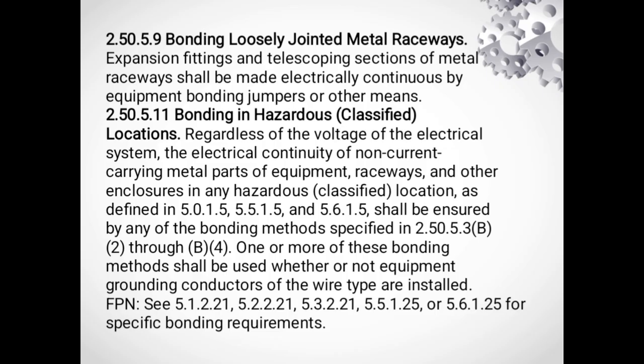2.50.5.9 Bonding loosely jointed metal raceways. Expansion fittings and telescopic section of metal raceways shall be made electrically continuous by equipment bonding jumpers or other means.